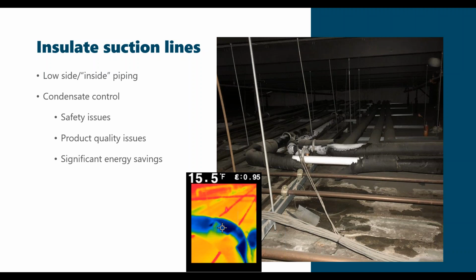So condensate control: you don't have condensate leaking onto a warehouse floor that someone could slip on and get hurt. Product quality issues: insulating the suction lines allows the refrigerant to stay at the proper temperature, so it's able to absorb the amount of heat that it needs to have your refrigeration system maintain temperature set point. Also significant energy savings, especially in low temp applications.